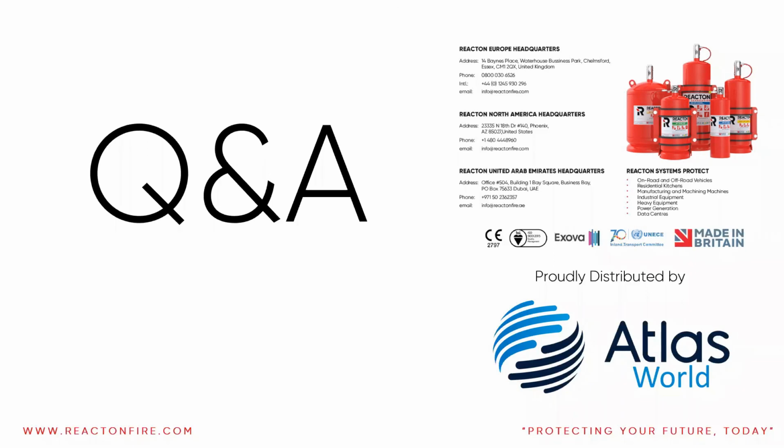So, how do we engineer the system, i.e., quantity of gas, etc.? Do you want to run through that quickly, Ed? Yes. So, with the systems, they're actually all pre-engineered, so there's no actual hydraulic calculations that need to be performed. As long as you stay within the limitations of our design manual, then that's fine. We know that they work. That's what we do all our testing for.